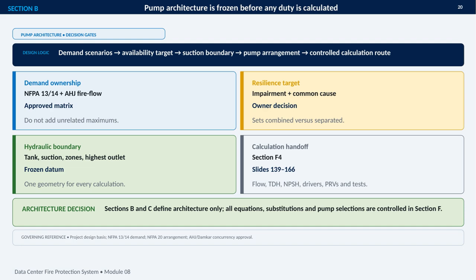First, demand ownership is defined through NFPA 13 and NFPA 14 requirements, together with AHJ fire flow expectations and the approved demand matrix. We should not add unrelated maximums. Next, the resilience target considers impairment and common cause risks, while the owner decides whether systems are combined or separated. The hydraulic boundary is then fixed around the tank, suction conditions, zones, and highest outlet. That creates one frozen geometry for every subsequent calculation, avoiding changes in the basis as the design progresses.